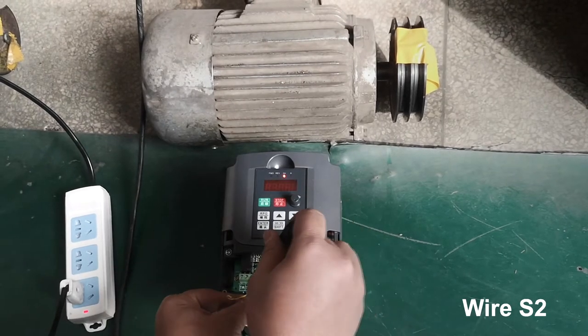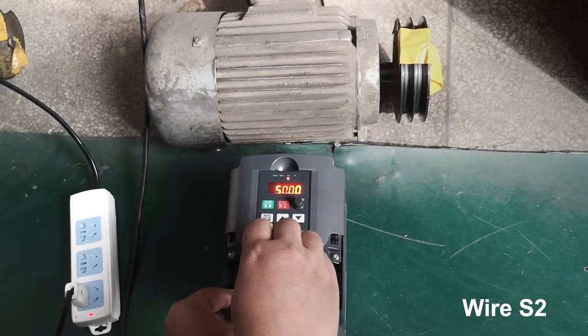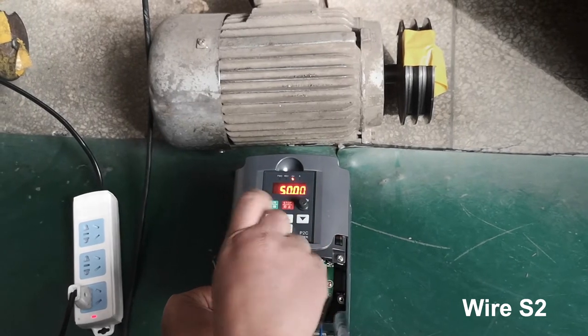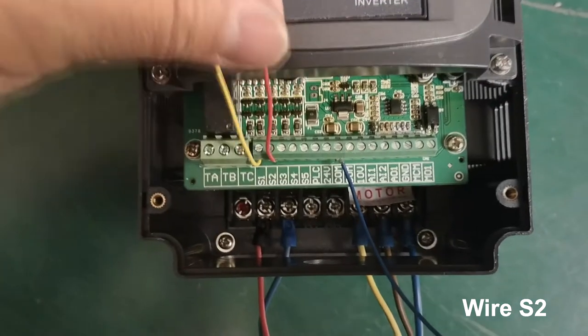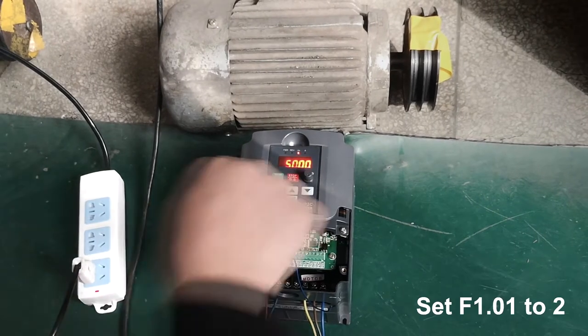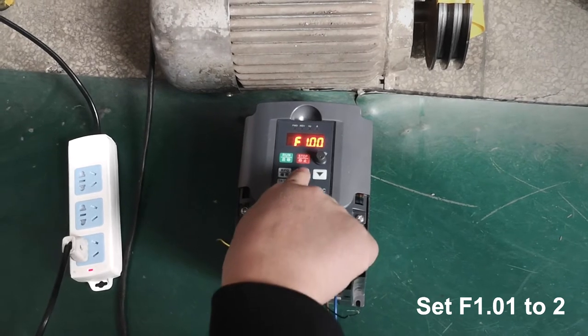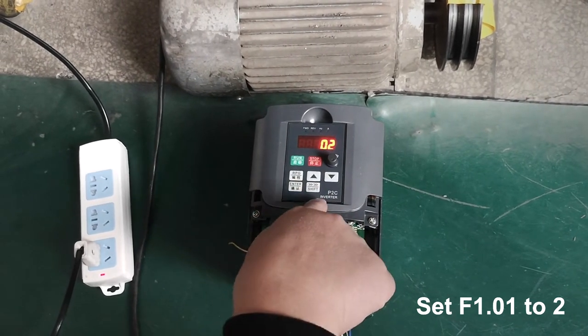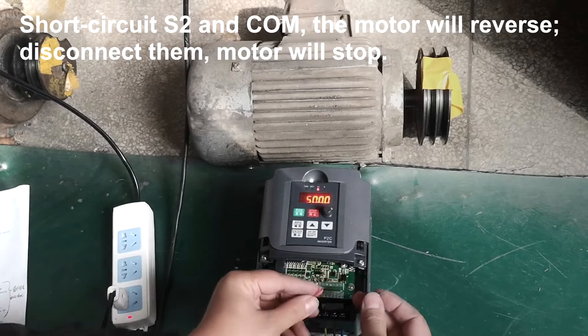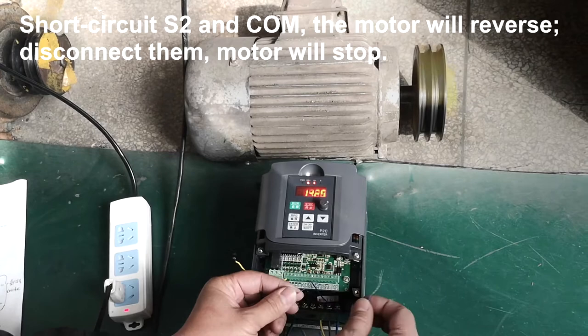Wire S2. Set F1.01 to 2. Short circuit S2 and COM — the motor will reverse. Disconnect them and the motor will stop.